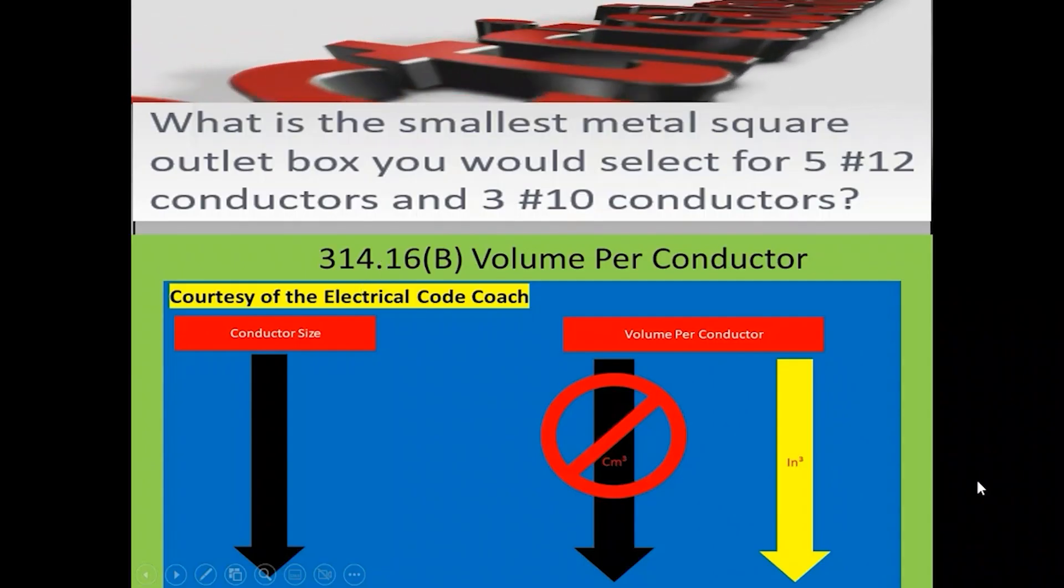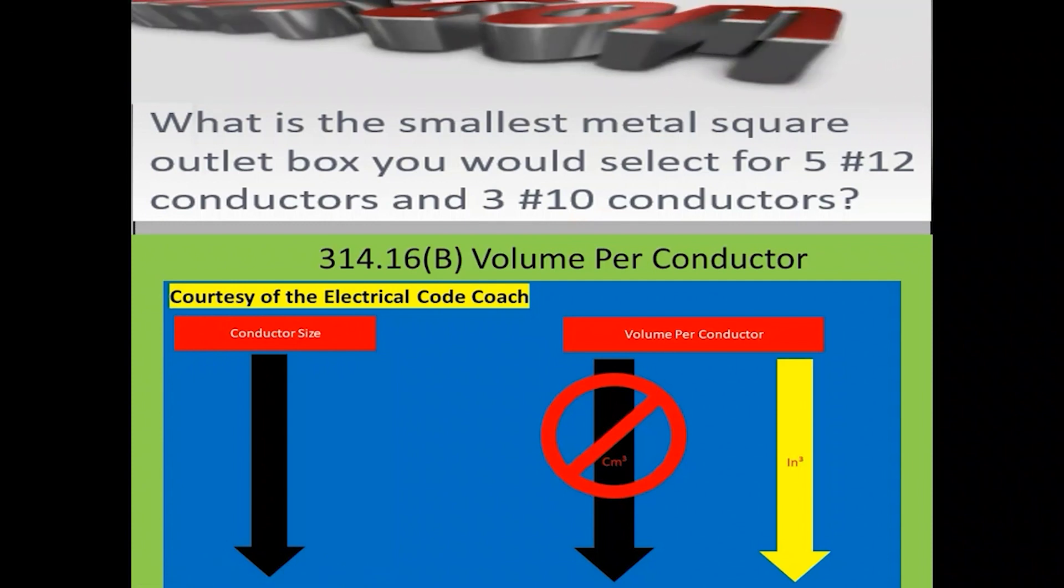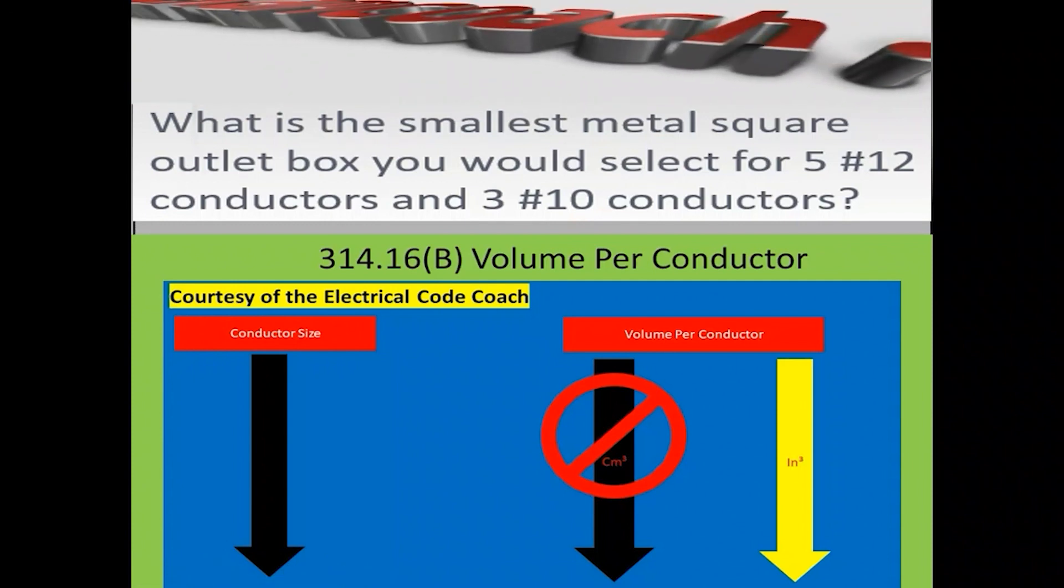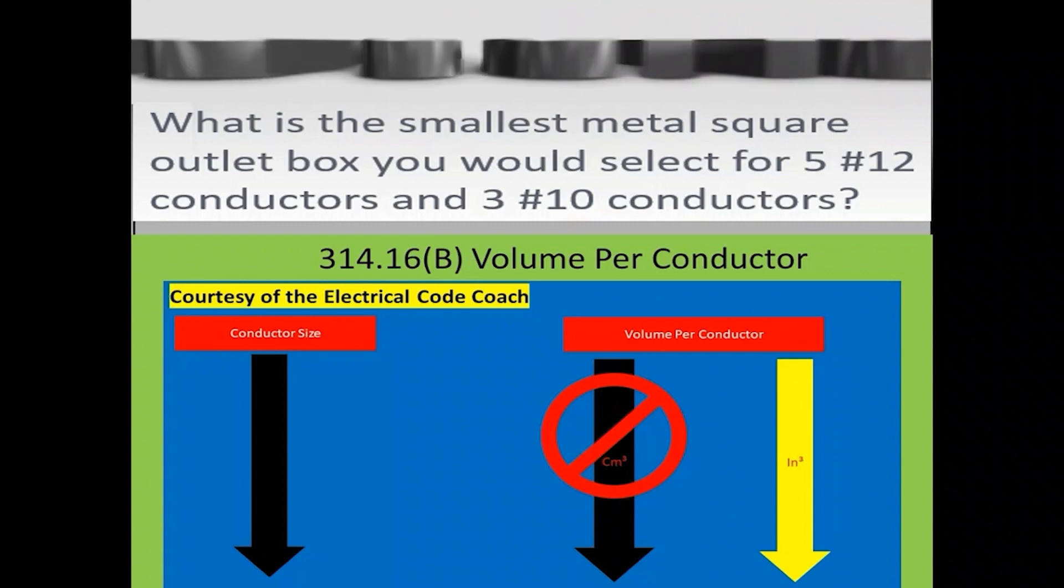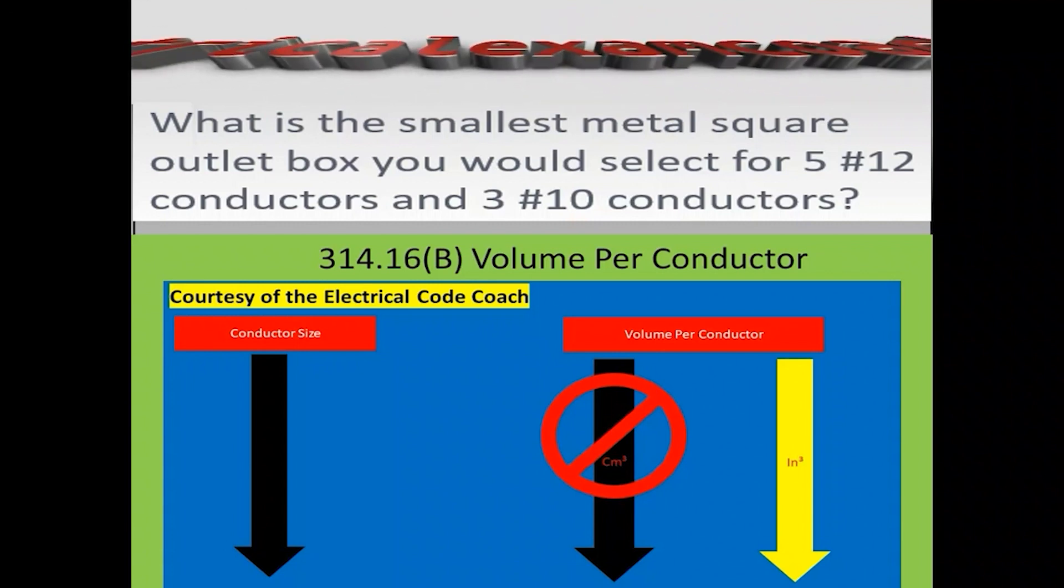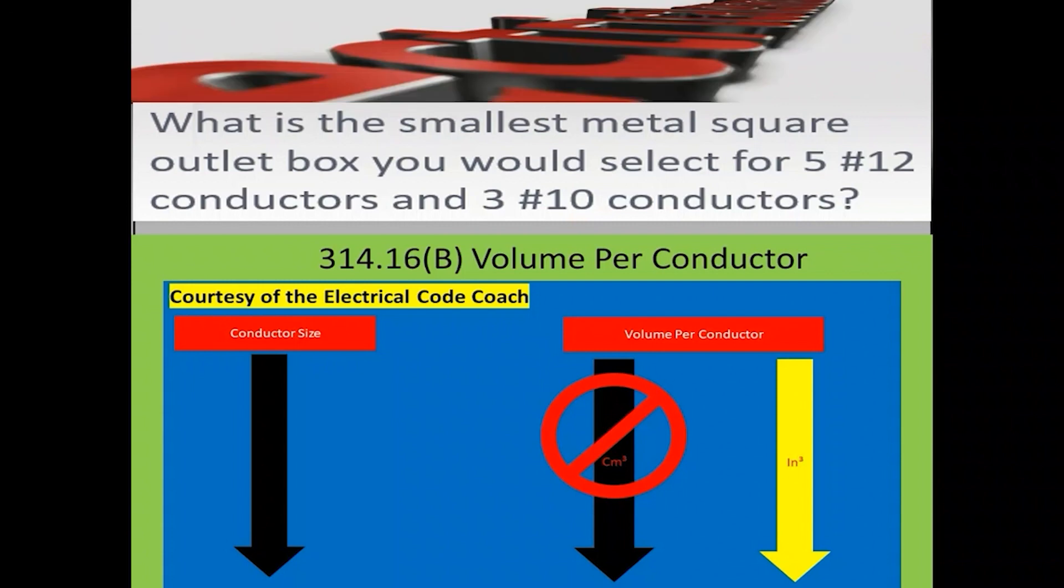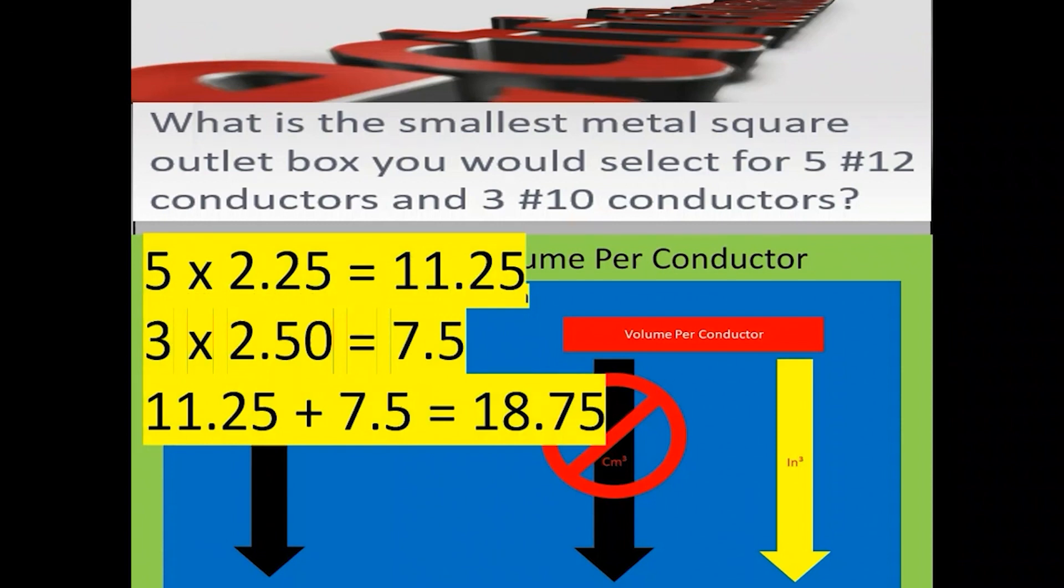For this one, we're going to head to table 314.16b first and we're going to find the cubic inch volume of each conductor. We start on the left-hand side and find a number 12 and come over to the cubic inch per conductor column and we're going to find that it's 2.25. We have five of those conductors, so we bear that math out and we get 11.25. We do the same process for the 10 gauge wires and end up with 7.5. We add those two together and that equals 18.75 cubic inches that we have that we need to fill a box with.